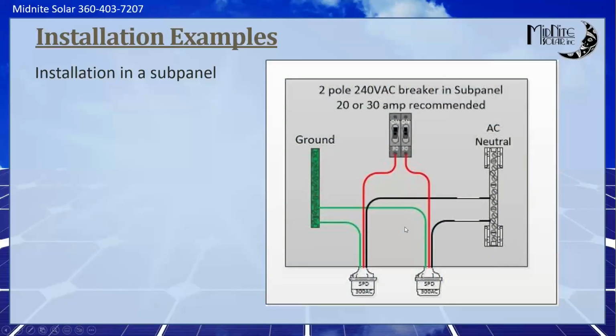Now, subpanels. This is where it gets interesting. So people think, hey, I've got one in my main panel, but I've got a barn out there that's 300 feet away, and I've got a great big woodworking shop, or a studio apartment in it. But it's protected because I've got one at the utility grid panel 300 feet away. My general rule of thumb is if you have a wire run longer than 50 feet, put something at the other end of that wire. So in this example of the barn being, say, 300 feet away, now all of a sudden, if there's a lightning strike nearby, that's induced voltage, it's going to head out to that barn and cause a lot of damage. So that is what we call a subpanel in the barn.